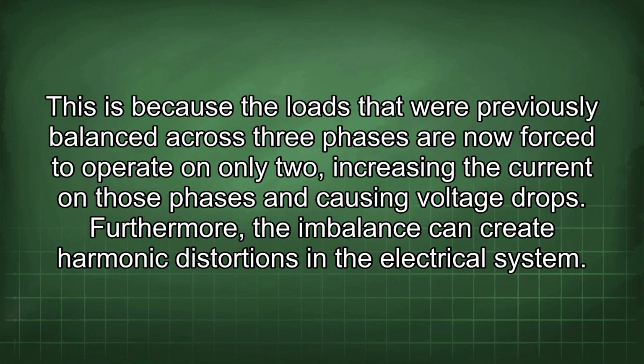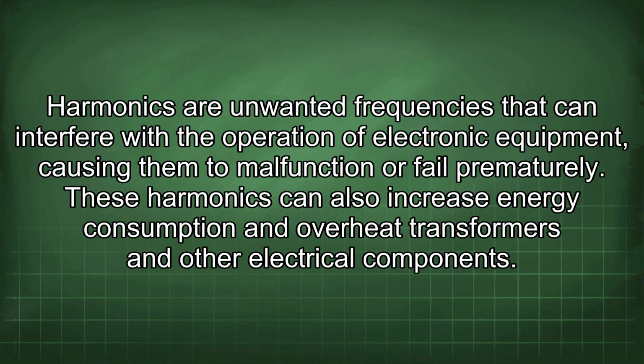This is because the loads that were previously balanced across three phases are now forced to operate on only two, increasing the current on those phases and causing voltage drops. Furthermore, the imbalance can create harmonic distortions in the electrical system. Harmonics are unwanted frequencies that can interfere with the operation of electronic equipment, causing them to malfunction or fail prematurely. These harmonics can also increase energy consumption and overheat transformers and other electrical components.